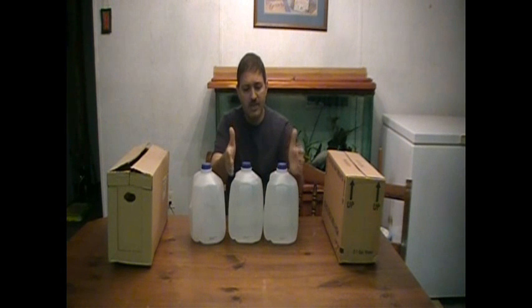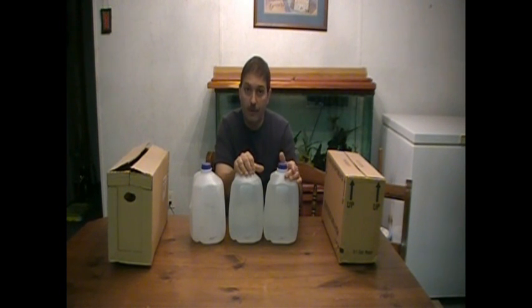And so we thought it was the drain pan. Most refrigerators and freezers have a condensation pan underneath the condenser coils, so that whenever the compressor's running and condensation forms on the coils, it just drips down into the pan, and then from there it evaporates. It's no big deal. So that's what we thought it was. It's just maybe too much condensation in the air, too much humidity, and the coils were getting a lot of condensation on them, filling the pan up.